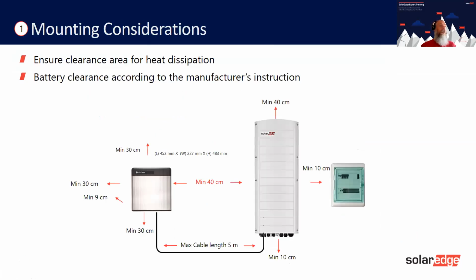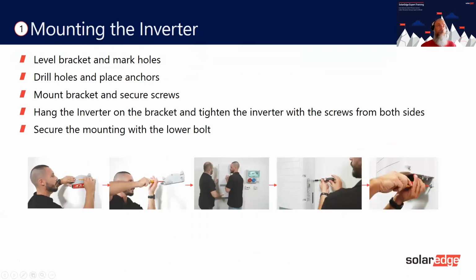So, installation steps, we're going to look at them. Maximum cable, I've told you, is 5 meters. We've got basically the mounting of it. So brackets: drill holes, put the bracket on the wall, tighten it, make sure it's level, and then hang the inverter on the wall. And then you secure the mounting with these nuts and bolts on the side. They actually go into the bracket.